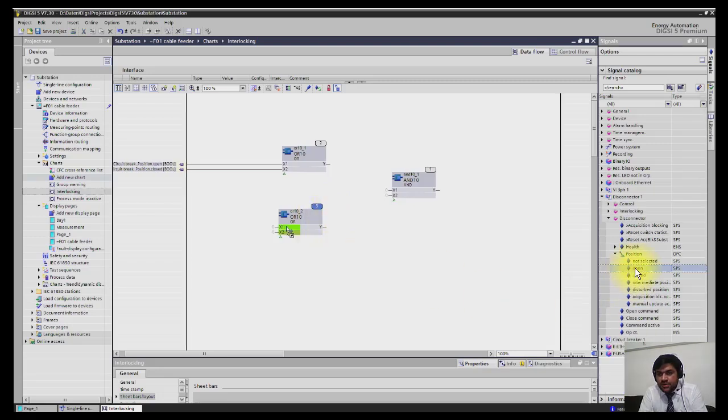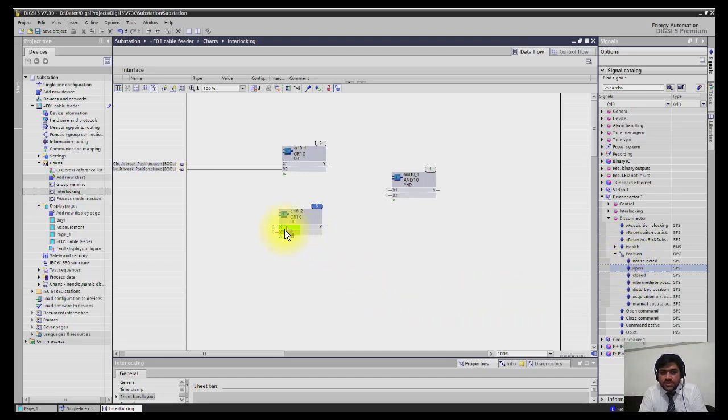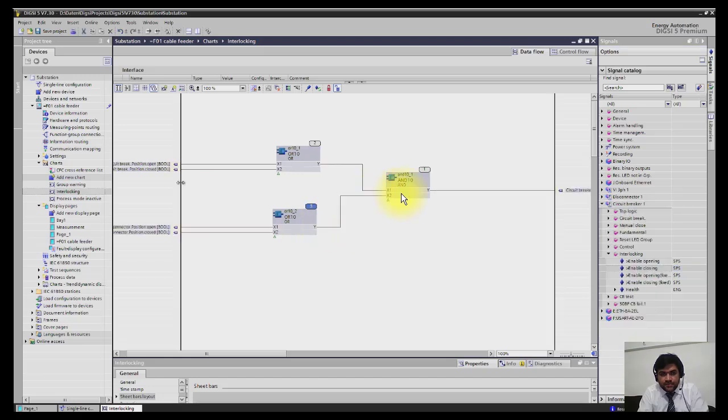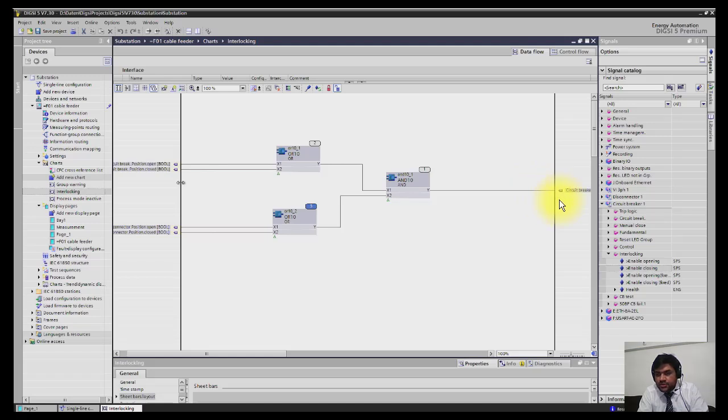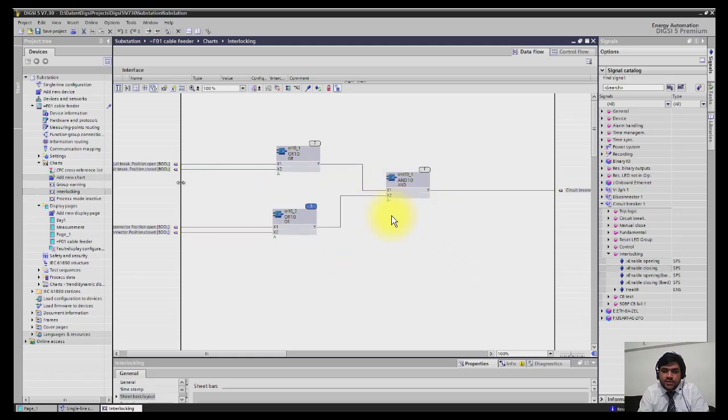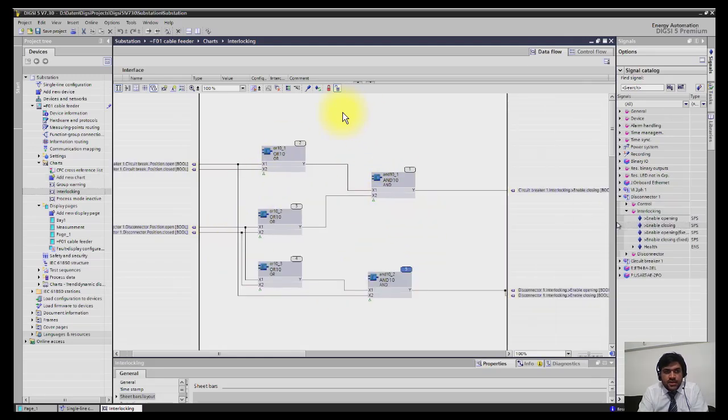In the same way I will now select open status of the disconnector and drop it to x1 and then close status, and then I have to just connect these two wires to x1 and x2. Finally I will connect the output of this gate, I have to just drag enable closing and drop it to Y. So now what happened, we should have a very clear status of isolator or breaker to operate the breaker itself. So this is how you are defining the logics. This is also super easy.